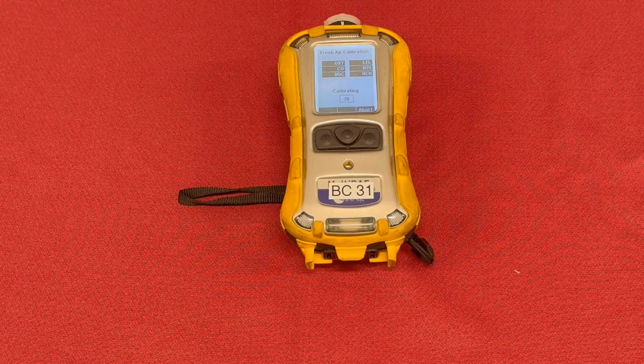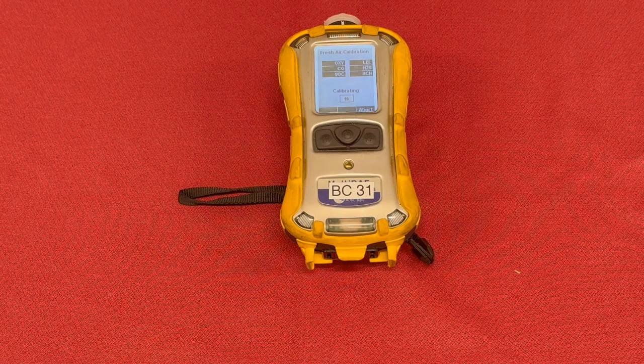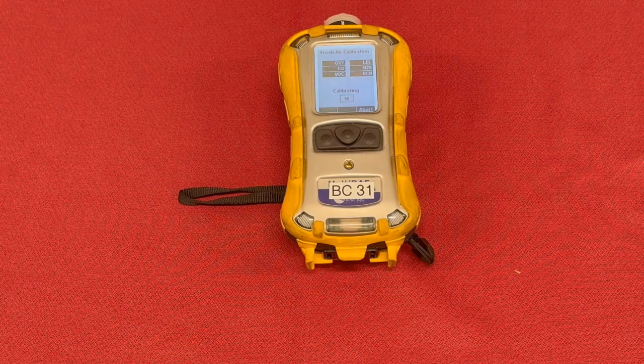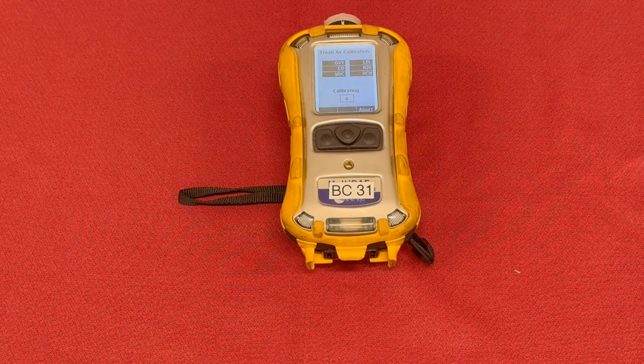If you start a fresh air setup, you can always quit and come back and do it again if you started it in a contaminated environment and you realize it. However, if you go all the way through the fresh air setup in a contaminated environment, what ends up happening is you've told your sensors that the air was clean, and once this is finished, it's supposed to start metering, and you've given them a false start point. So it actually throws all your readings off from there.